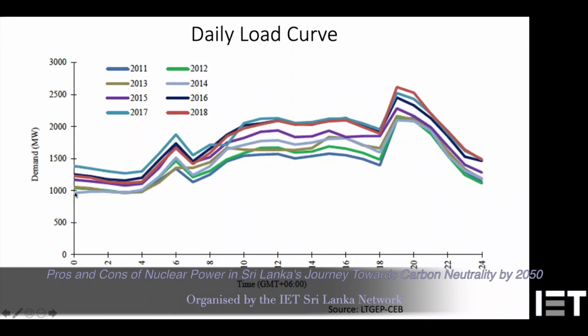But look at the blue line, the 2014 line, where demand was about 1,000 megawatts, so 25% is 250 megawatts. Therefore we had to derate our 300 megawatt Norochcholai unit to 250 megawatts during this early morning low demand period. That means you are losing economy, your efficiency is going down. But you can see this early morning demand is about 60% of the peak demand.